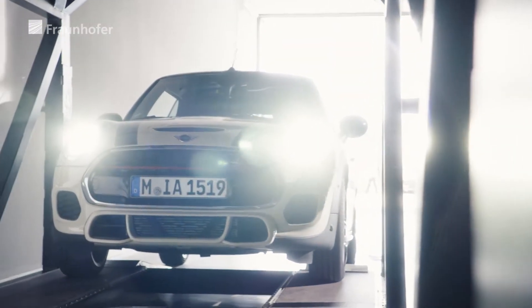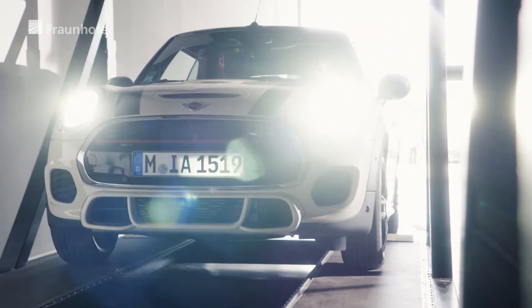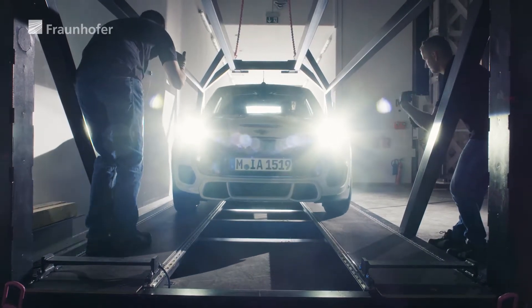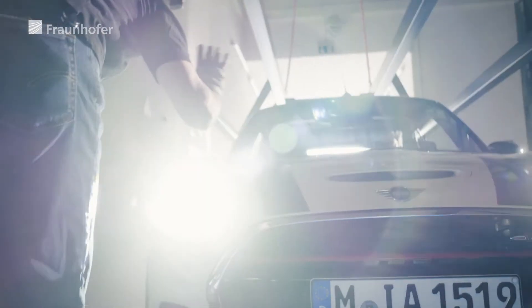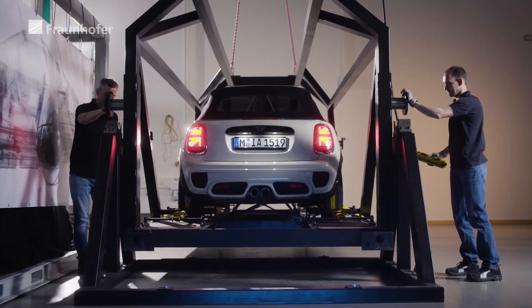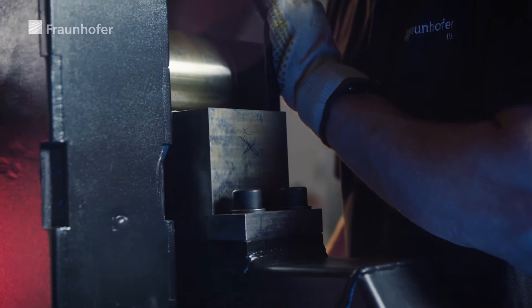This name is actually too small for the sheer magnitude we can now scan. If you use computer tomography nowadays, you might use it for fist-sized parts or in the chest area — this is the standard size people use. But beyond that, almost nothing is available, because the power is simply limited. We surpass that with this unique system, using special components that generate such a high radiation output that we are able to penetrate very large objects.